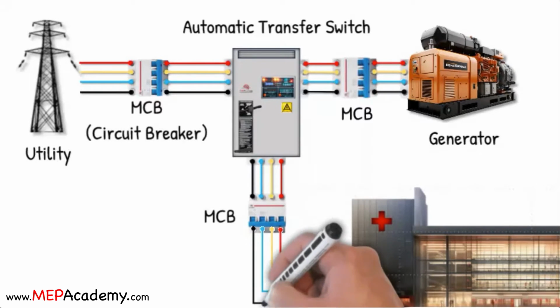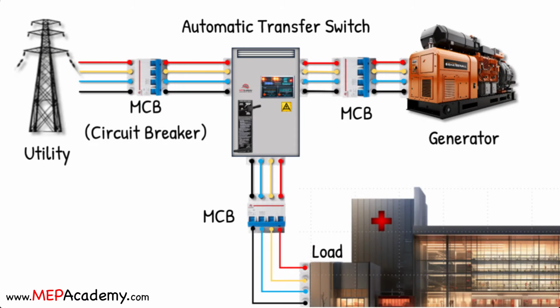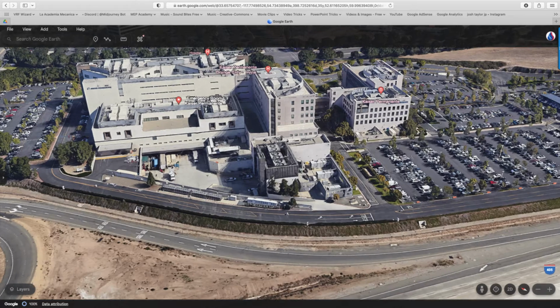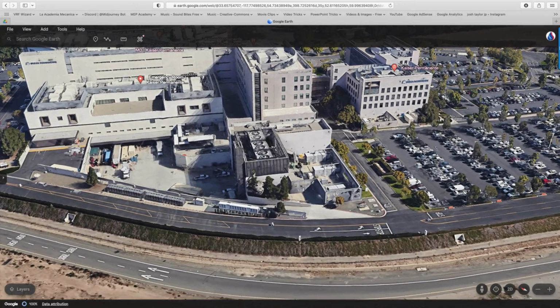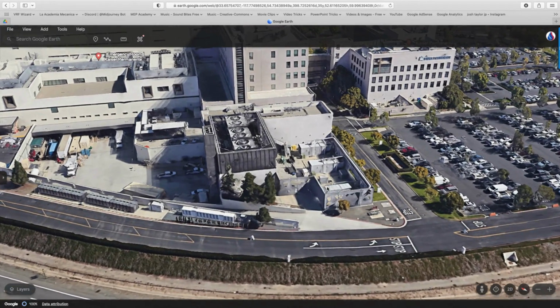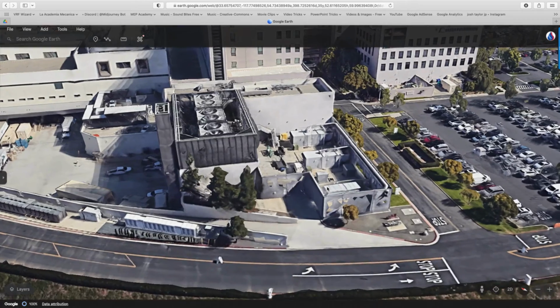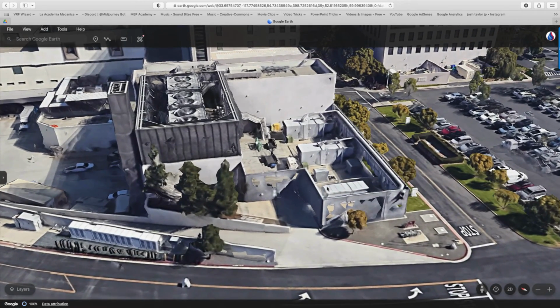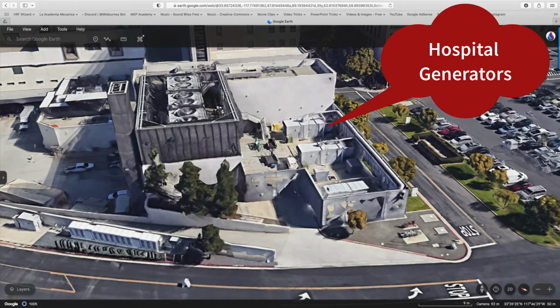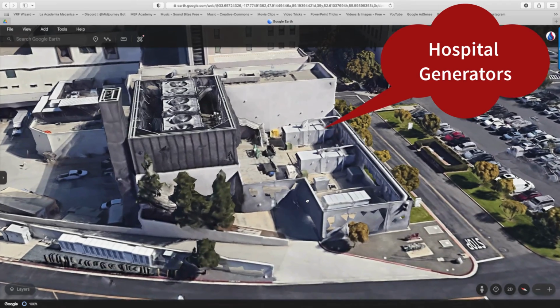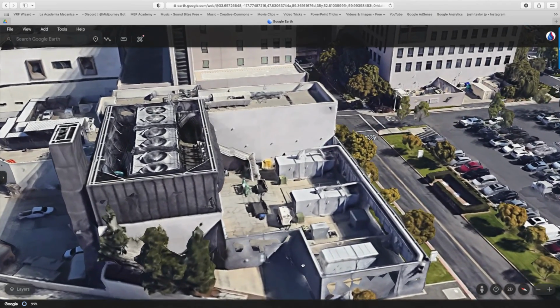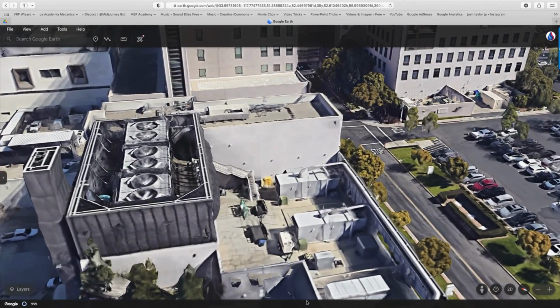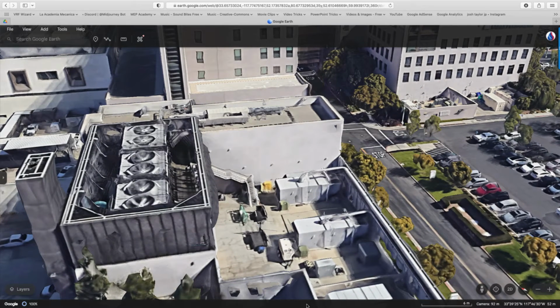ATS systems are equipped with sensing devices that continuously monitor the voltage and frequency of the primary power source. When the controller detects an interruption in the primary power supply, it automatically initiates a transfer to the secondary source, typically a generator. This swift response is critical for applications such as hospitals and data centers, with the transfer occurring in less than 1 second.